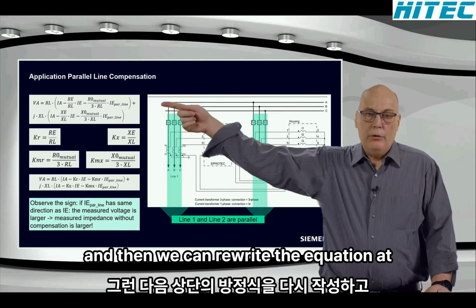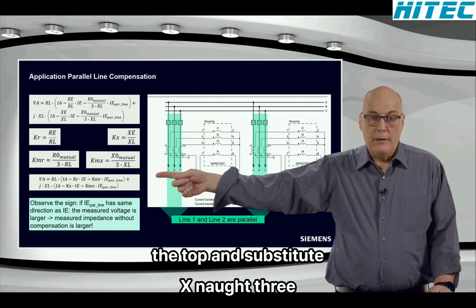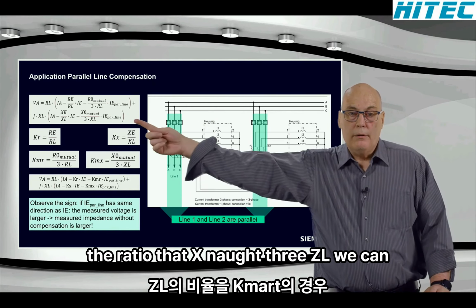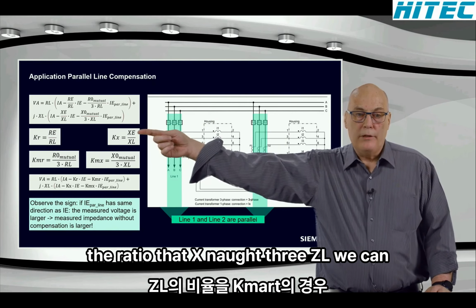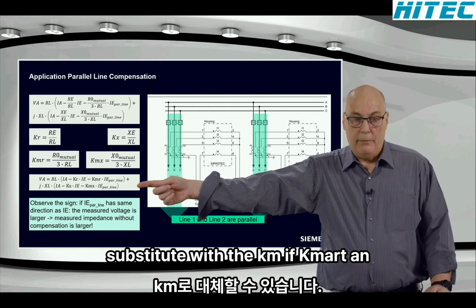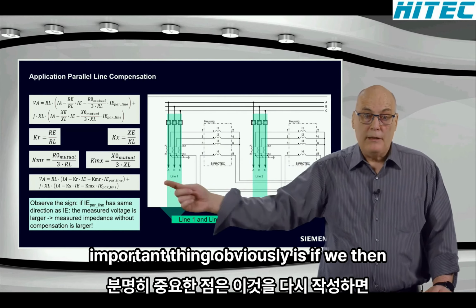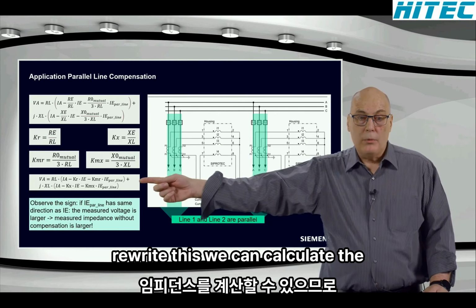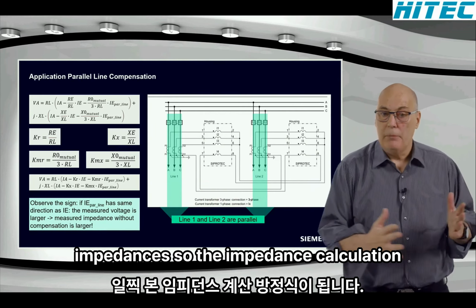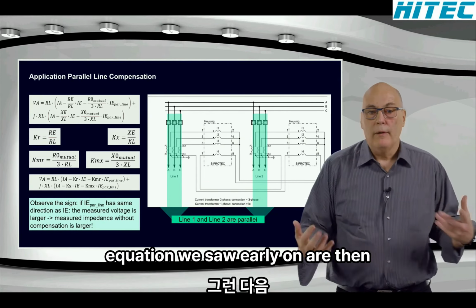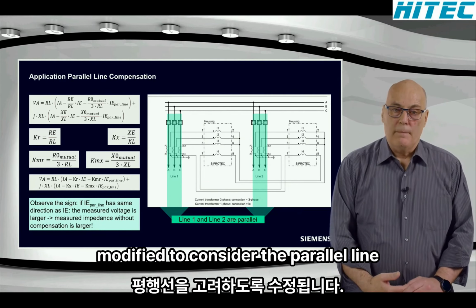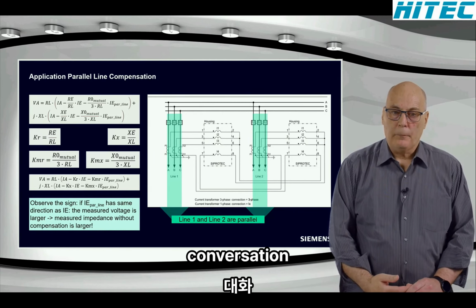And then we can rewrite the equation at the top and substitute the ratio ZX0 over 3ZL with the KMX, KMR. And the important thing, obviously, is if we then rewrite this, we can calculate the impedance. So the impedance calculation equation we saw early on is then modified to consider the parallel line compensation.